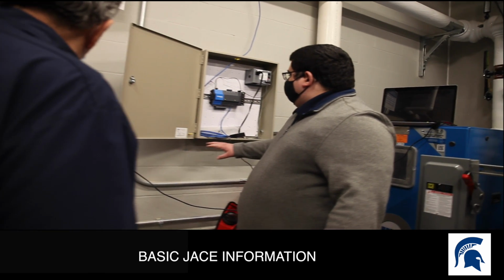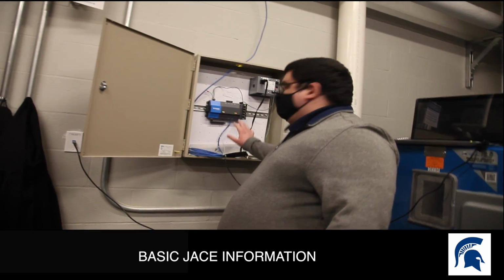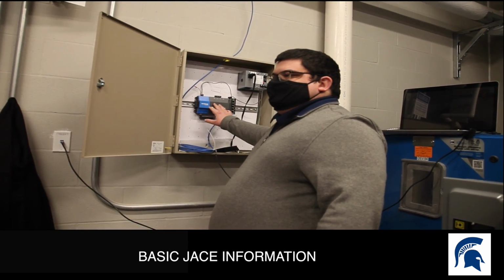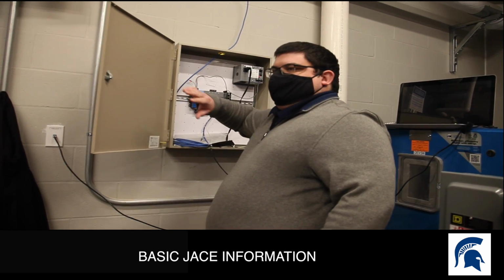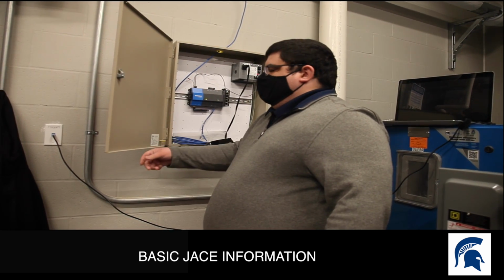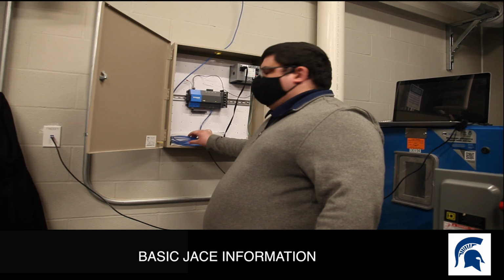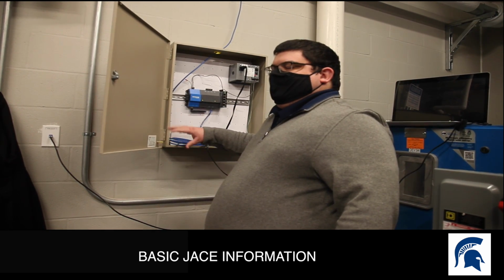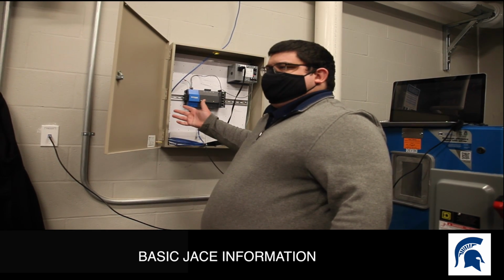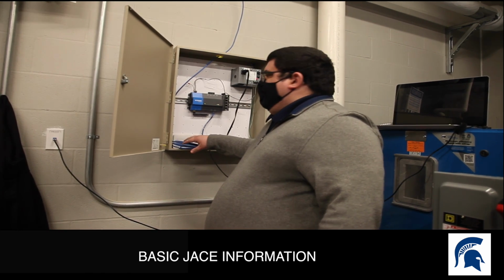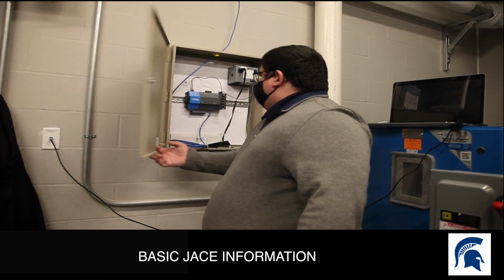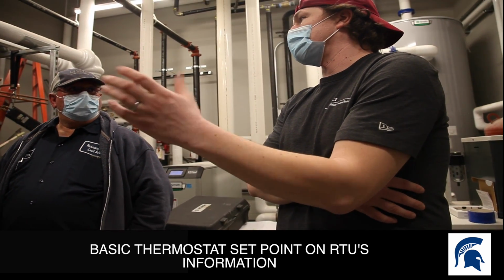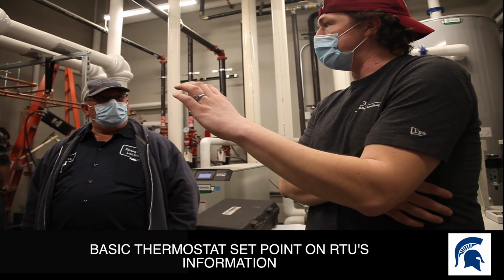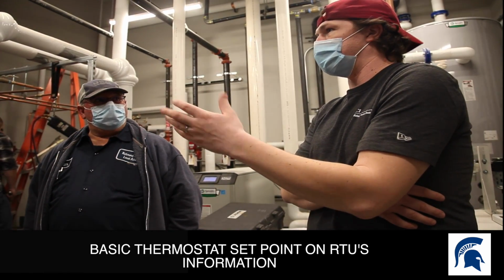If you ever hear anybody refer to a Jace, this is what they're talking about. Okay. This provides communication to all the control equipment that's out in the building. It's accessible over the network in the building and externally. So if you guys have a VPN or anything like that, you can get to it through there. There is a discharge air set point on those RTUs, which I believe is 55.